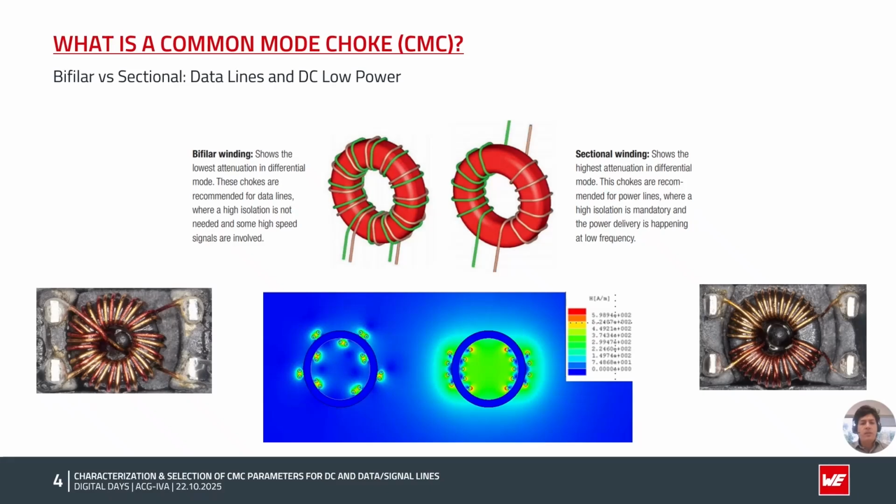Here in the picture, we show you an example from a simulation that illustrates the leakage inductance of each winding style. As you can see, it's much higher in the sectional winding. This is due to the separation of the windings.